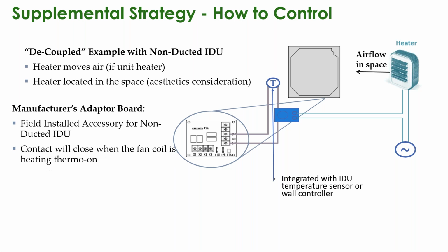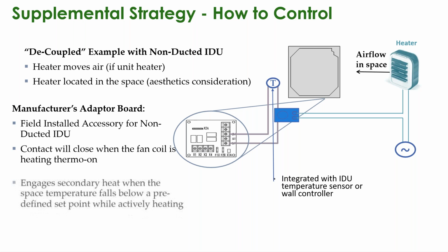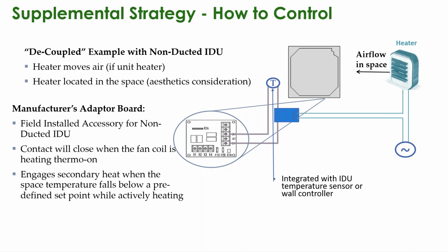It integrates with the indoor temperature sensor or the wall controller, and the contact is able to close when it is in a heating thermal on state. It engages that secondary heat when the space temperature falls below a predefined set point. And again, this logic is all going to be specific to the manufacturer of choice.